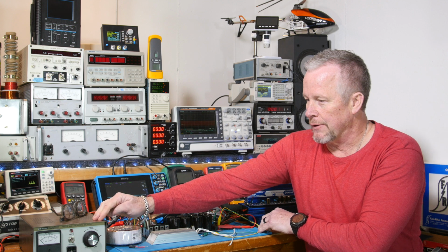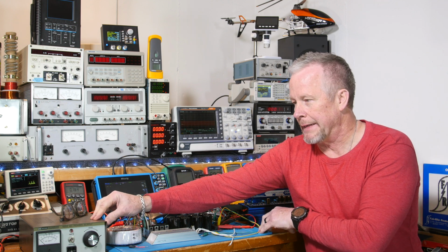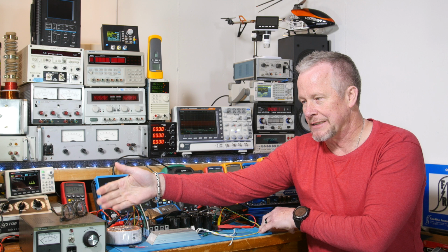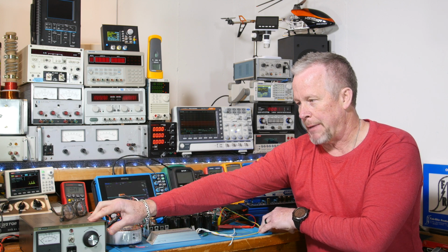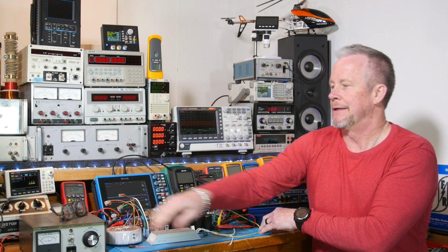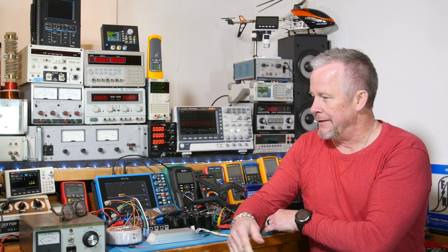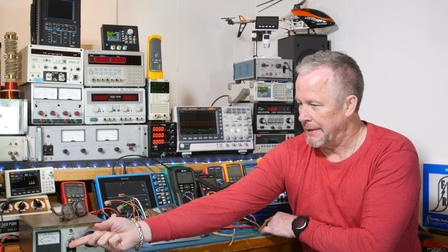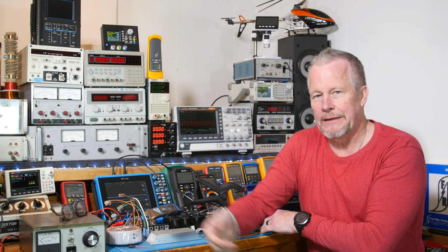Well, this guy's a 300 VA supply, so it actually has some impedance, so we won't get a true reading. That's one of the things that's wrong: testing with a power source that has too much impedance. You might say, I'm going to set this up and hit the on switch and that should work, but the impedance in that messes it up.